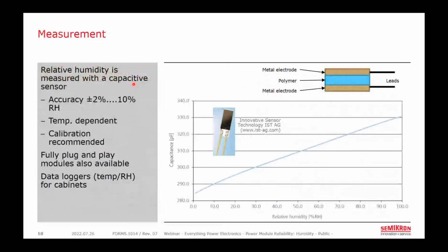Now, one of the reasons relative humidity is referenced in all the environmental specifications is that it's relatively easy to measure. On the other hand, there's no equipment for measuring absolute humidity directly. It's always calculated indirectly using relative humidity, temperature, pressure, etc. So for relative humidity, a capacitive sensor is formed using 2 electrodes with a layer of polymer in between serving as the dielectric. The dielectric constant of this polymer changes as water molecules move into it, thus changing the capacitance of the sensor. You can see that the response of such a device is pretty linear with relative humidity.